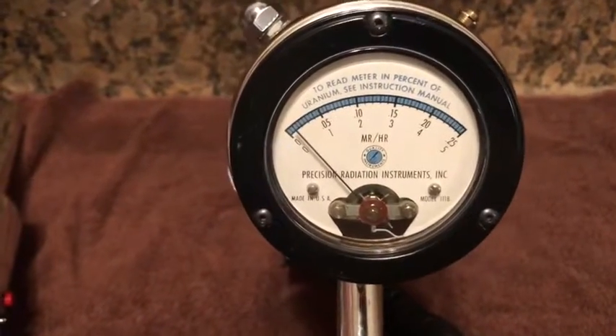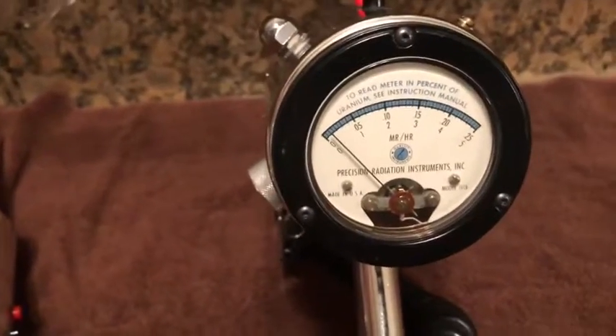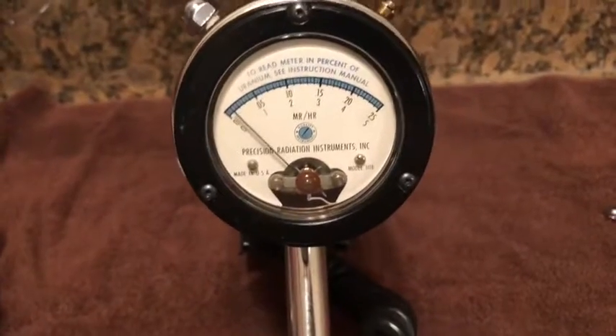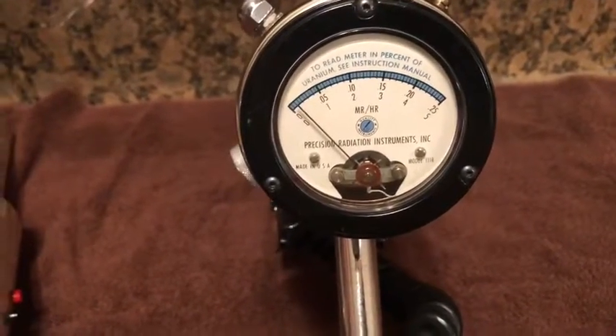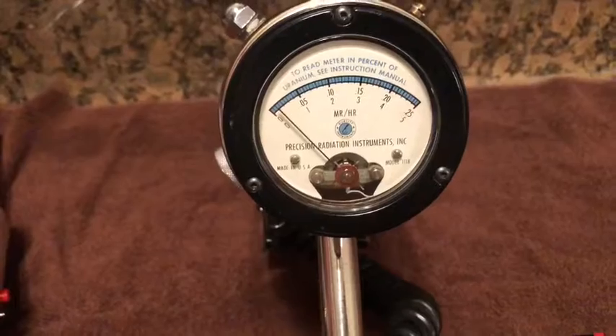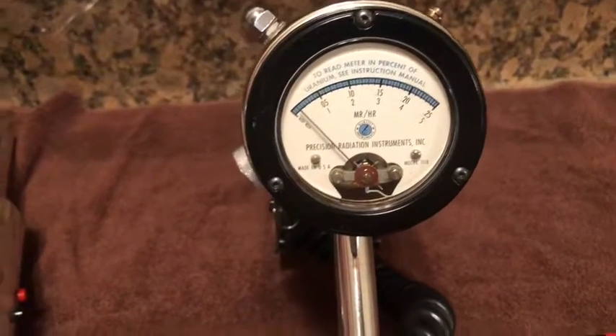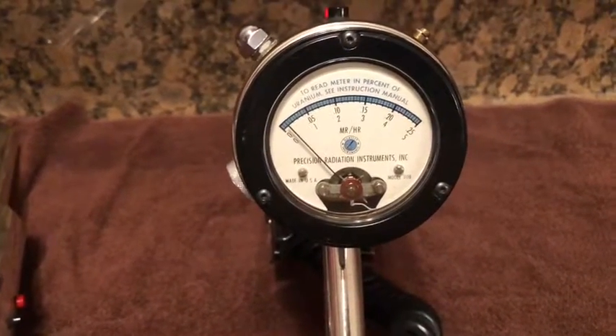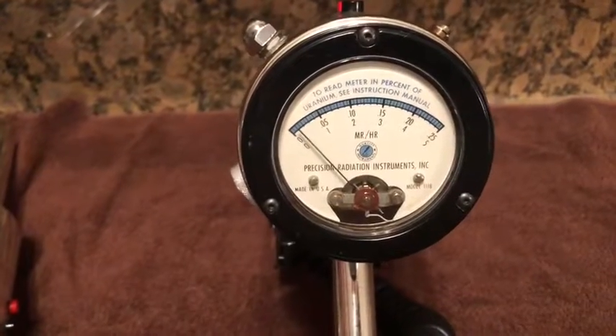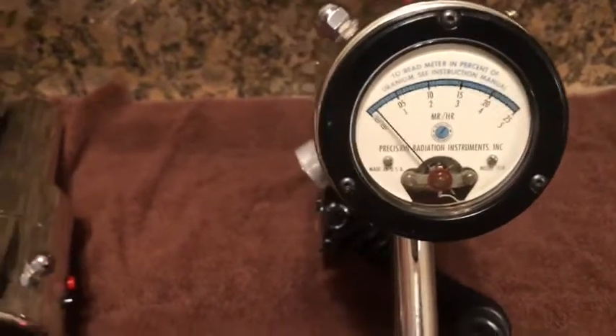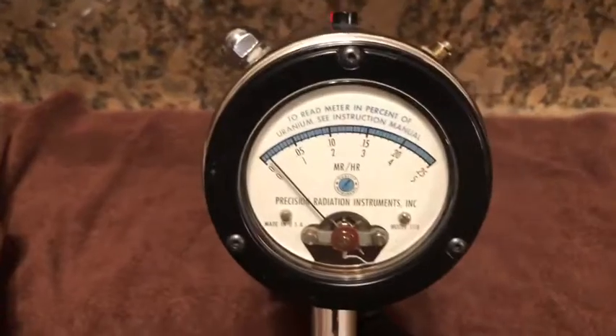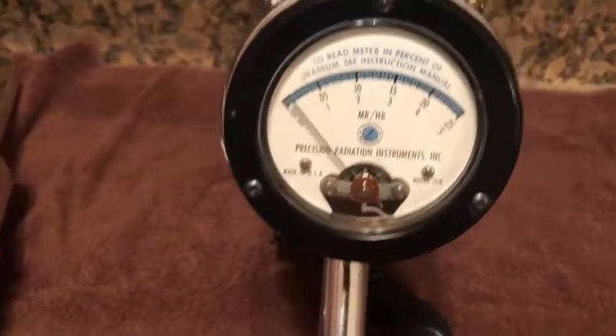Mike Wall and myself have been going back and forth trying to calibrate one of these things as best as possible using a test source. And it's kind of hard. These things just do not respond very well to getting absolute accurate calibration using a test source. You can get pretty darn close, especially with the ones that came with it.